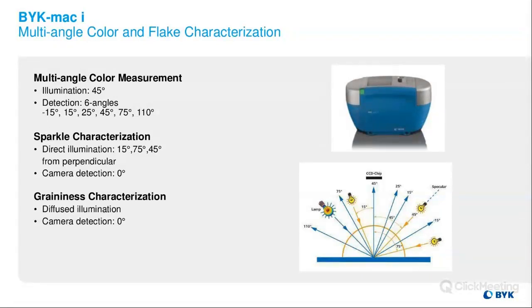Even when it comes to solid colors, often we can look at a surface and think that it looks uniform, that there's no directionality to it, but often there is some directionality depending on how it was painted or coated or printed. We can't pick up on that with the naked eye, but the spectrophotometer will. So the answer is yes, you can use this instrument at the 45-degree angle, and it will measure very close to a 45-0 instrument. But you need to be consistent with the direction that you're taking the measurements in. Good, good. Hope that helps, Ashley.